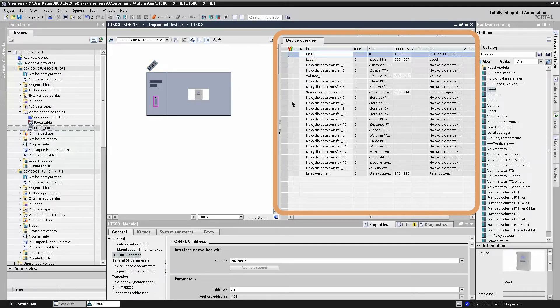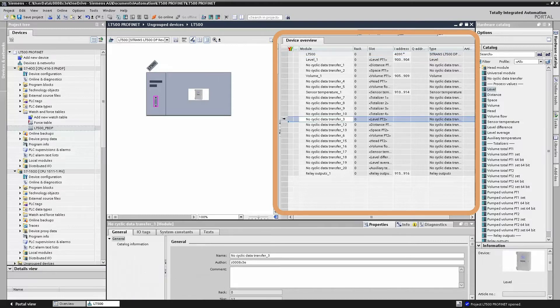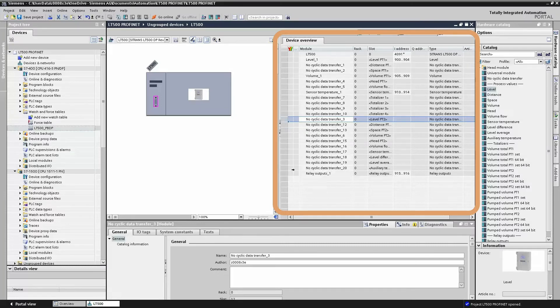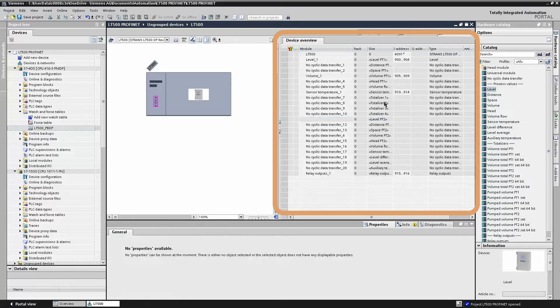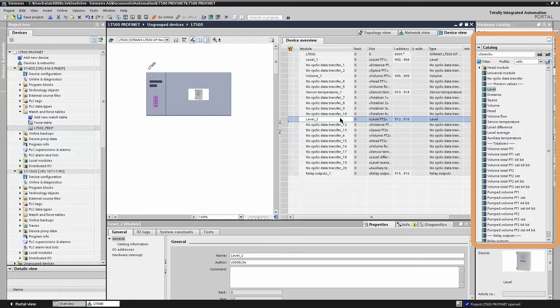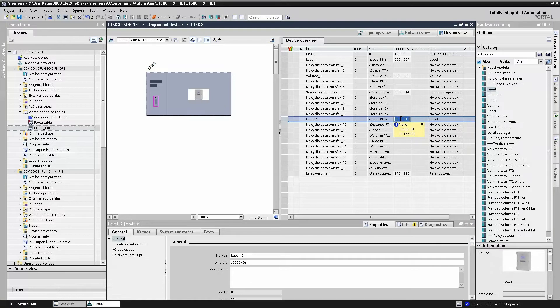But again, we can add additional process variables to our list as well. A little bit different here, we actually have to remove the empty slot before we can add in the new process value. So we can actually just delete the module here, then go and take the process value we want from the list and put it in the appropriate slot. We simply add the IO address. This is the address that the PLC will use to store that value.